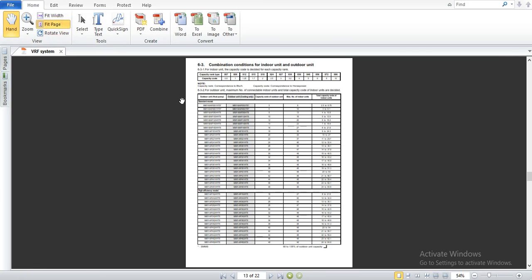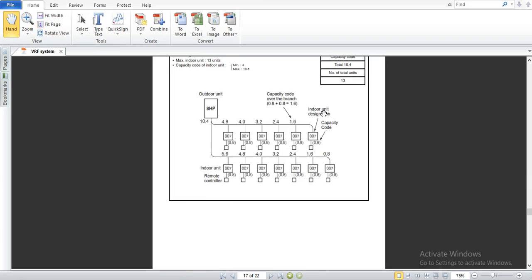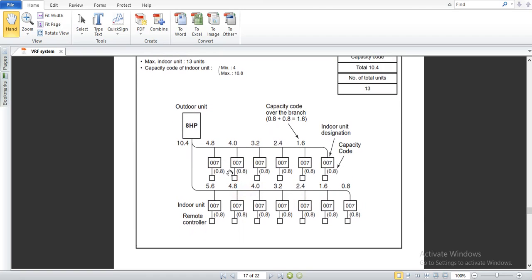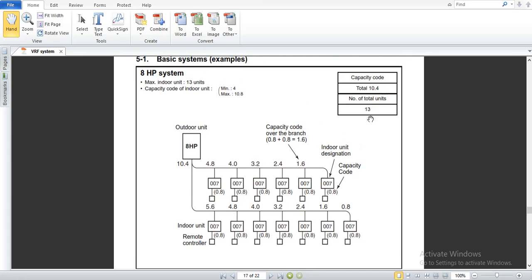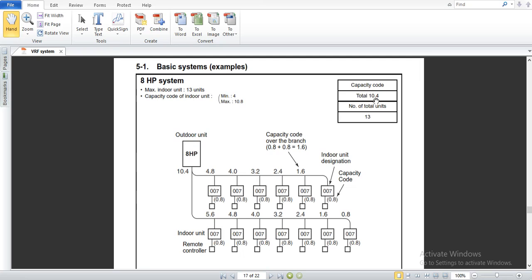Let me explain with one example. We have 13 indoor units in our project. Each indoor unit has a capacity code of 0.8 horsepower. One group has a total capacity code of 4.8 and the other group has 5.6, giving a total capacity code of 10.4. So the total capacity code of the indoor units is 10.4.